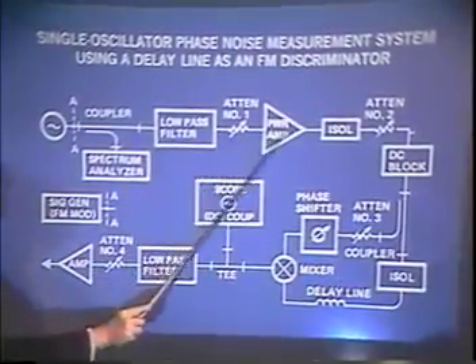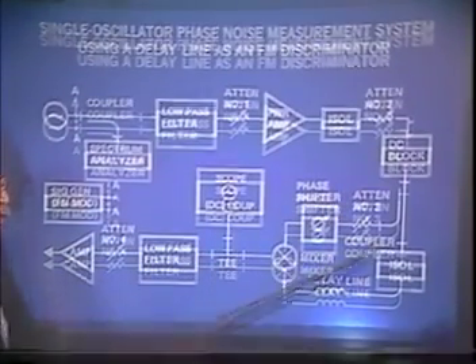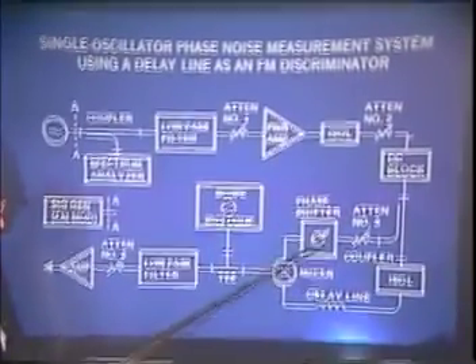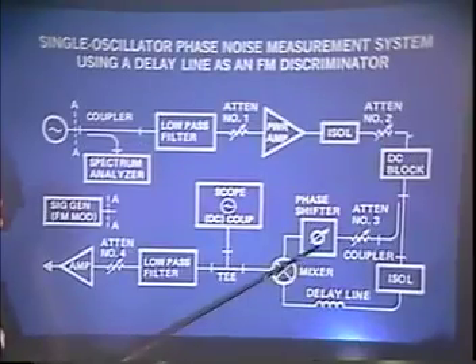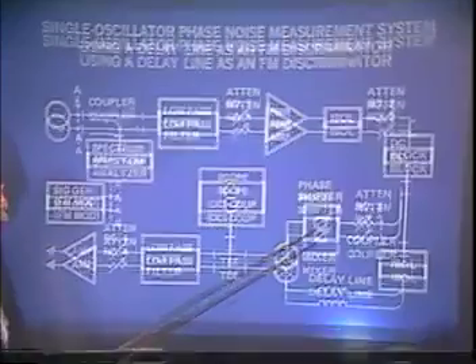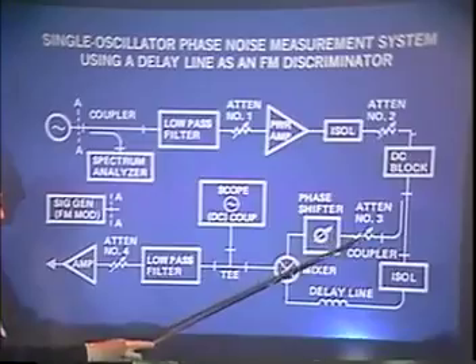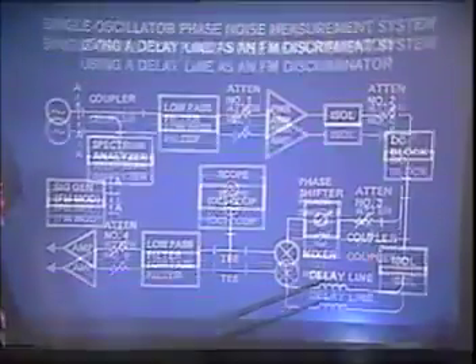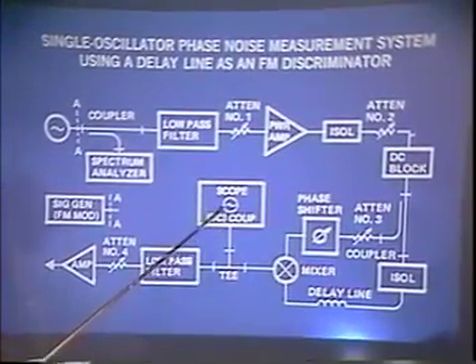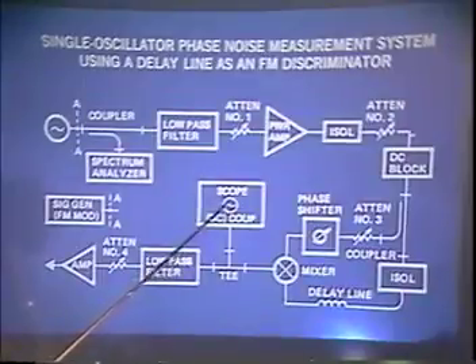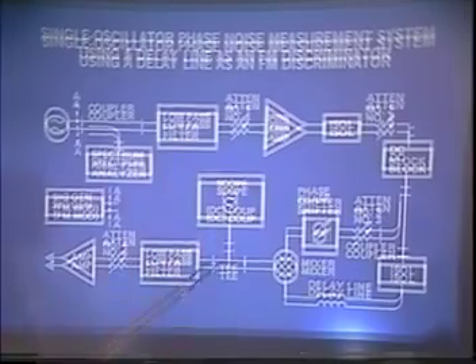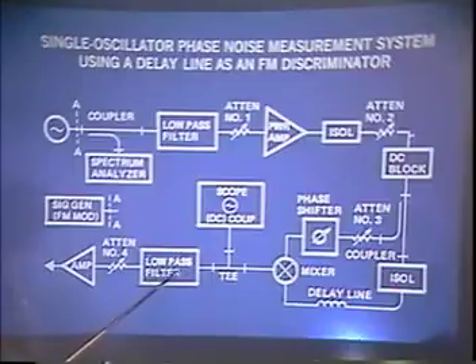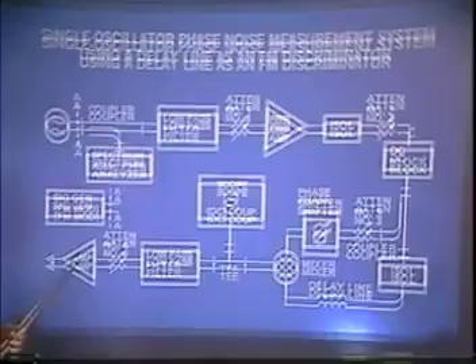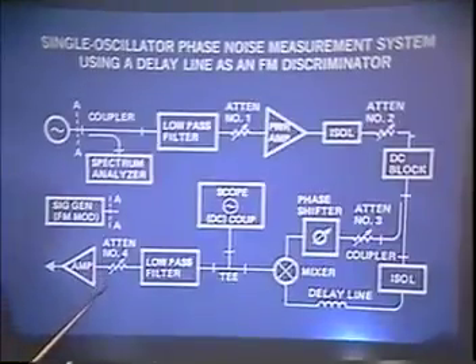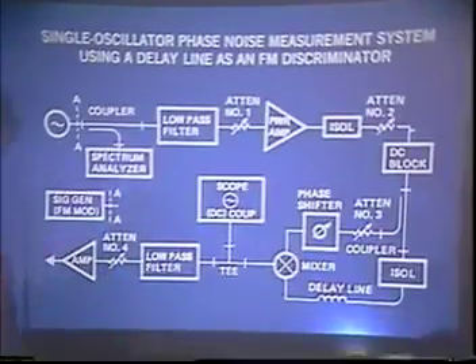All the rest of this is just attenuators and isolators and DC blocks for the system. But here's your delay line portion here. You saw that for this we had that trombone in the system we just looked at. We have, for setting levels, an attenuator. Delay line over here. The DC scope, again, you put this so that you have here a straight line on this scope representing DC. Into a low-pass filter, an attenuator in the system. This is the attenuator you set to high values of attenuation when you're performing the calibration.